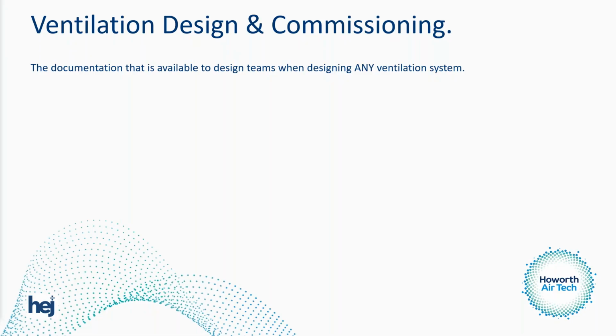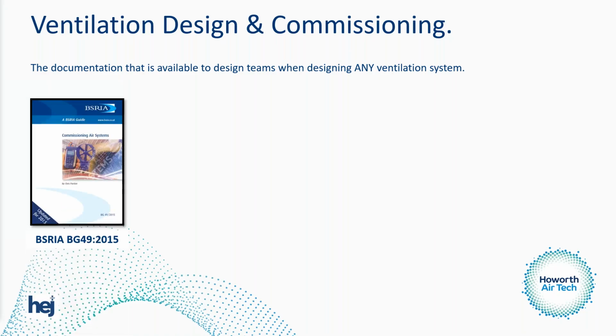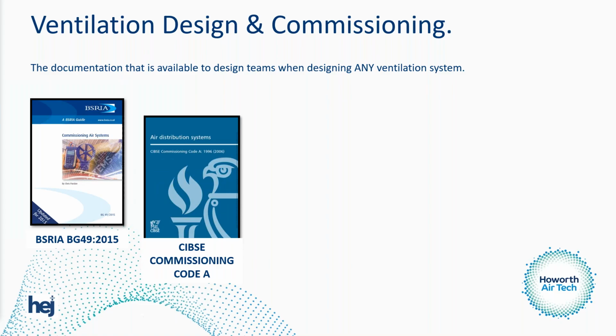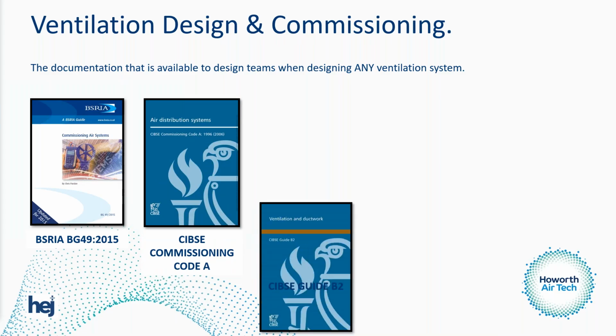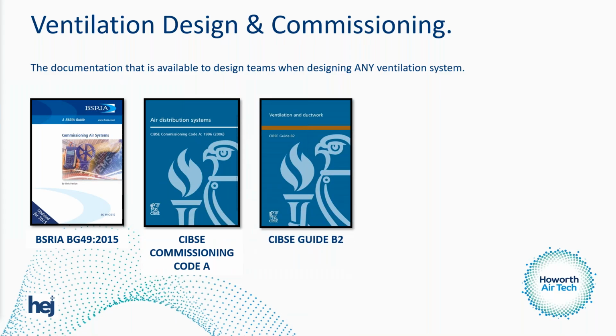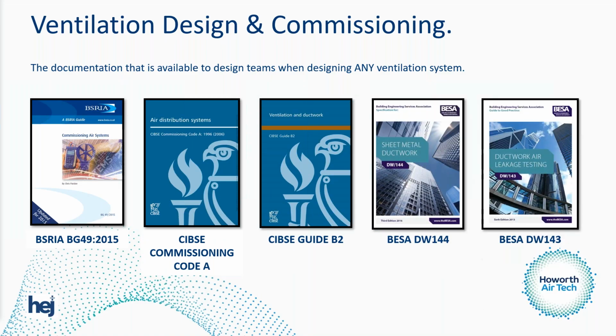So the documents that I want you all to be aware of, and if there's something that you're going to take out of this webinar, then go away and have a look at these documents. The first one is BSRIA BG49. It's a key document that we use in all our validations, and it's something that I cite a lot within my work. CIBSE Commissioning Codes of Practice is a big one in the industry. Ventilation and Ductwork Guide B2, and then we have DW144 and DW143 from BESA. These two documents are for the installation of ductwork and ductwork pressure testing of the system. So they're also really important documents that we're going to touch on today. But the one we're going to focus on is BG49.